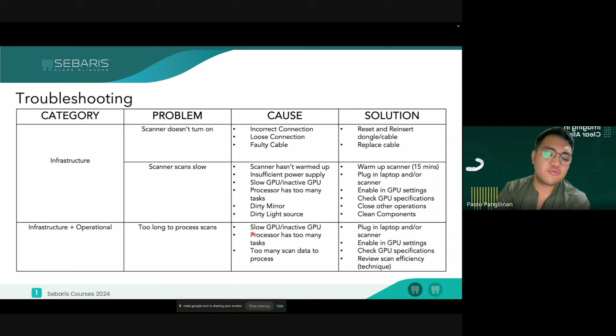Now, this is one common problem that most, let's say, in Sebaris or even for me, when I'm doing my aligners, this is the common problem that they also get: double images. The reason why you can have double images on your scan is because you have a dirty mirror or a dirty light source. It's rarely because a scanner is not calibrated. Usually it's a dirty mirror and dirty light source, so the main solution is literally clean it up. I use microfiber for that.